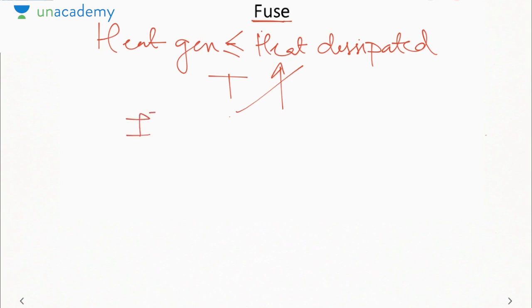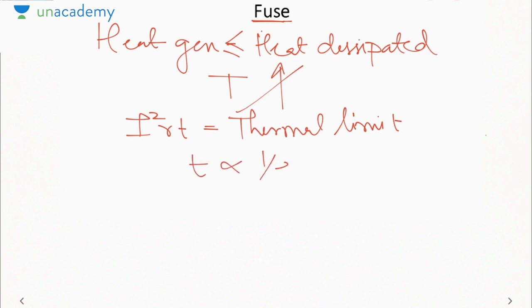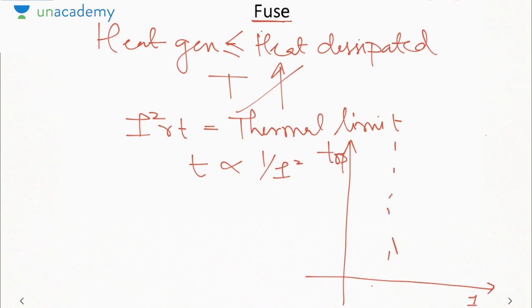Now, if we see this equation, I square RT is equal to thermal limit, that means time is inversely proportional to I square. Now usually when we plot the characteristics, we plot T operating versus current. Now as I told you, there is a minimum current below which the fuse does not operate. This is your minimum fusing current. Okay, and the characteristics will be hyperbolic. As evident from this equation, characteristics will always be inverse or hyperbolic. So this is the purpose of the fuse. It is used as a backup protection and it always operates whenever the heat generated is greater than the thermal limit of the fuse.